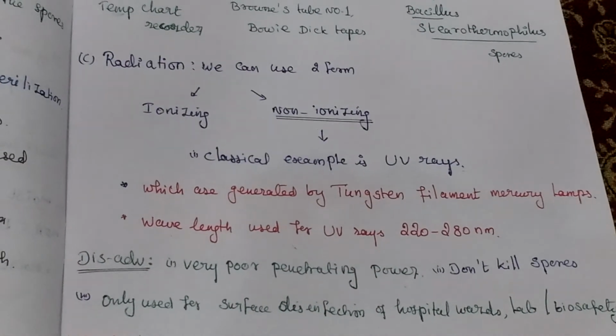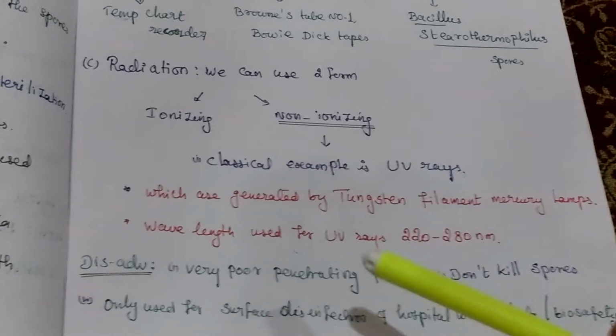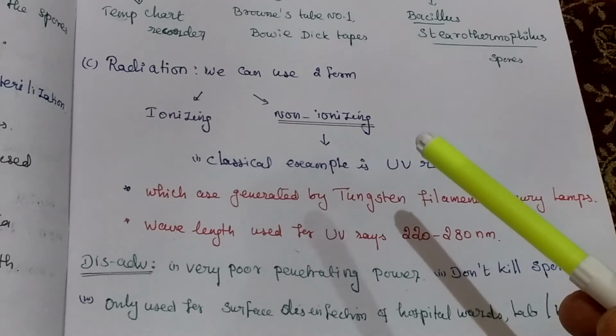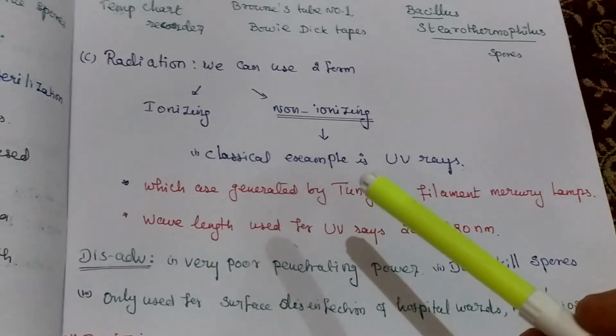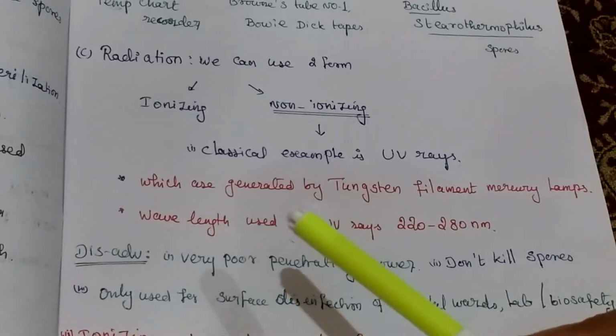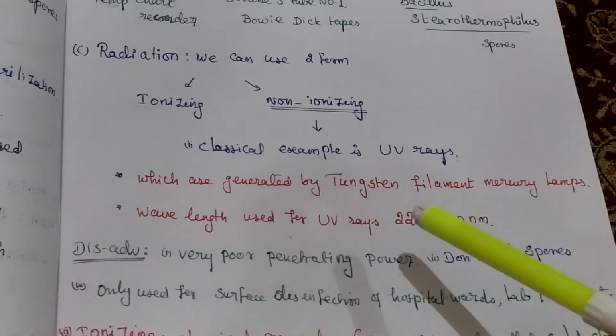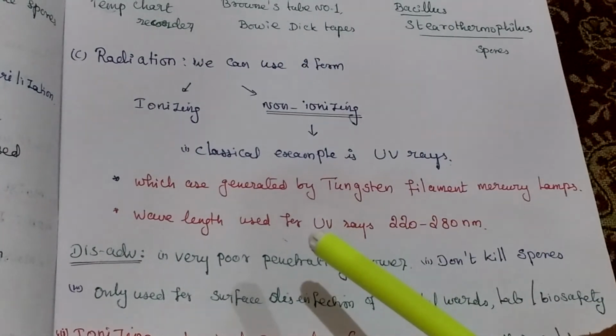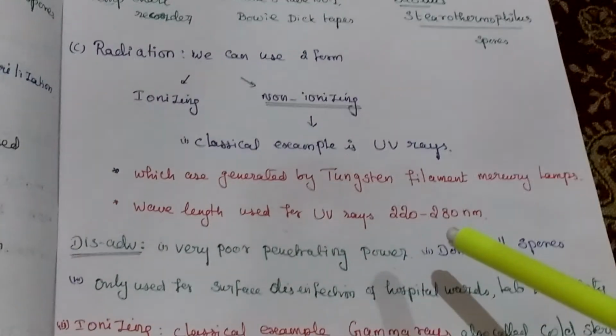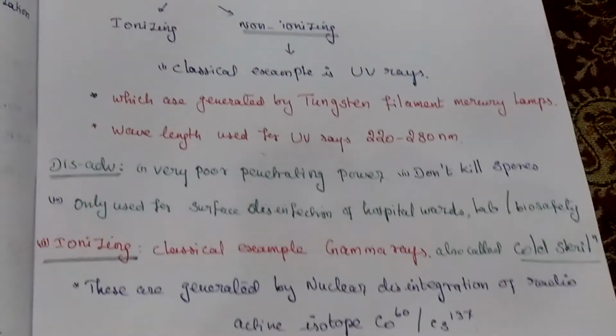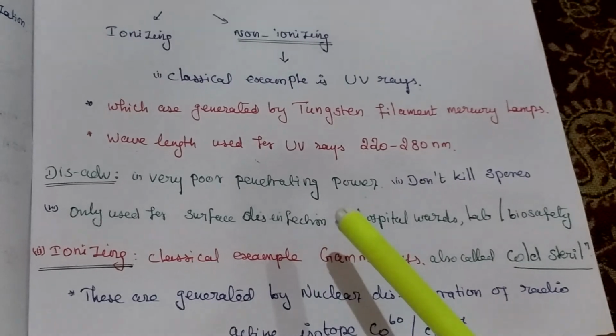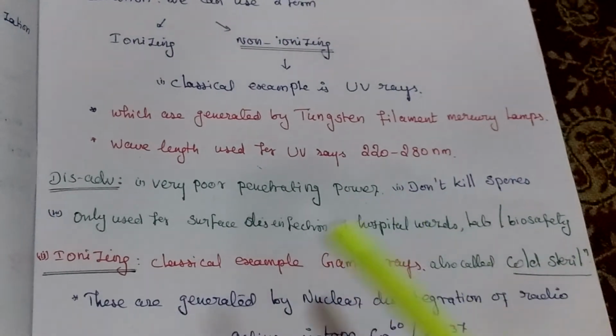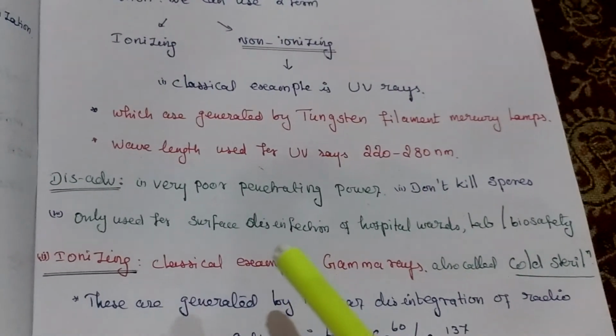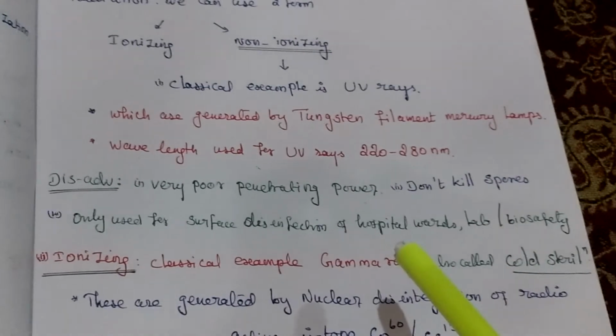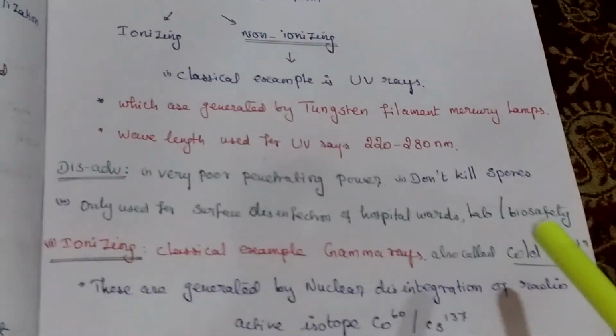Last one is the radiation method. Here we are using two forms of radiation, ionizing and non-ionizing. Non-ionizing radiation, the classical example is UV rays, which are generated by a tungsten filament mercury lamp. Wavelength used is 220 to 280 nanometers. Disadvantage: very poor penetrating power, doesn't kill spores, only used for surface disinfection of hospital wards, labs and biosafety places.